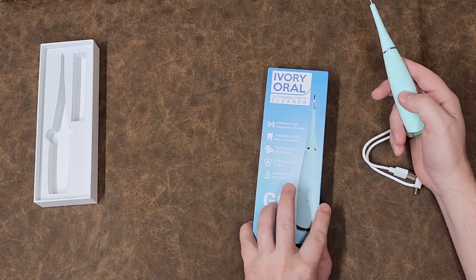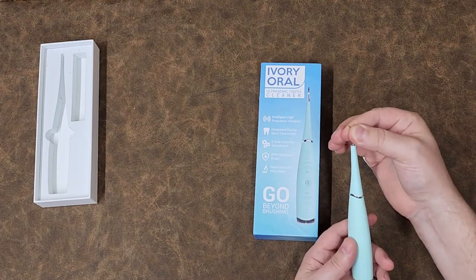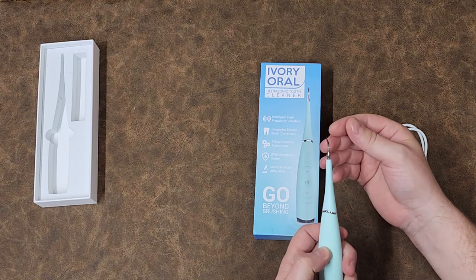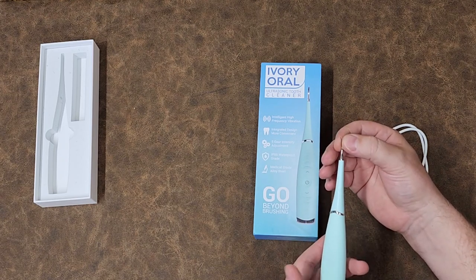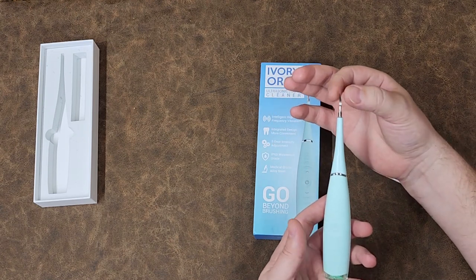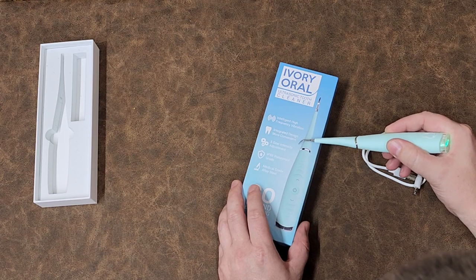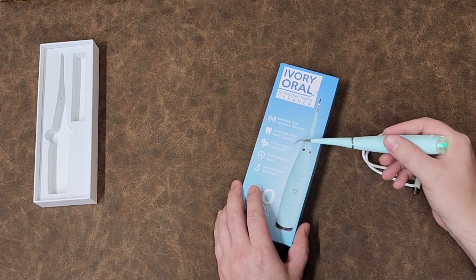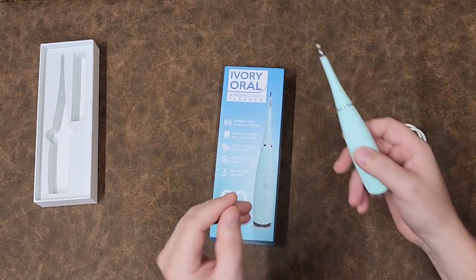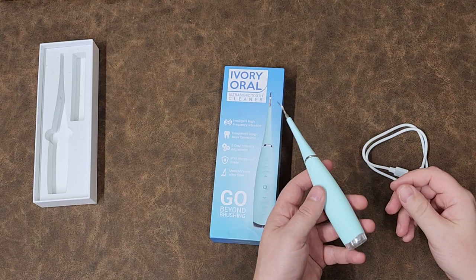That's the difference from an ultrasonic prophylaxis. Because of the way it's tuned, if you try to hold onto an ultrasonic prophylaxis you are going to burn your fingertips — the vibration creates friction in your tissue. I can turn this guy on high and as soon as I pinch it a little bit, you can hear the tone change because I'm changing how the wave propagates through the stalk. It takes little to no strength, and it almost immediately dampens out. An ultrasonic prophylaxis will never dampen out like that — it takes a lot of force.